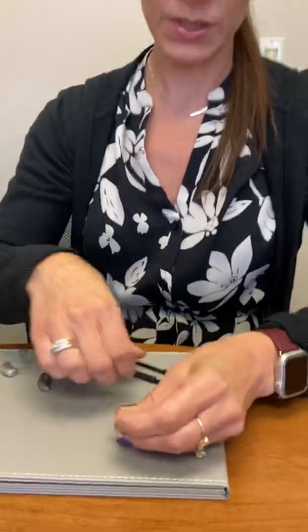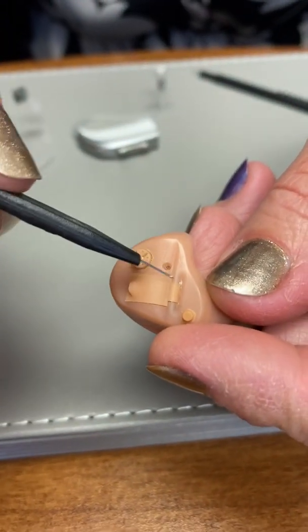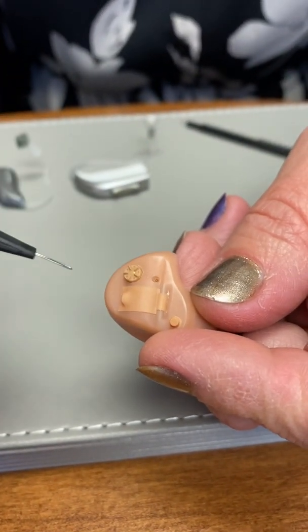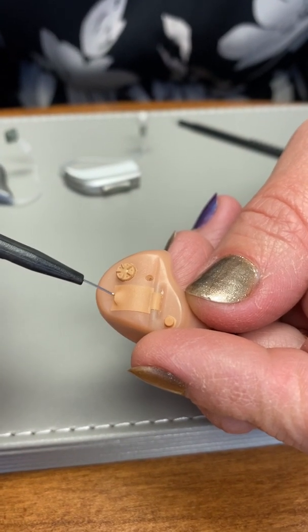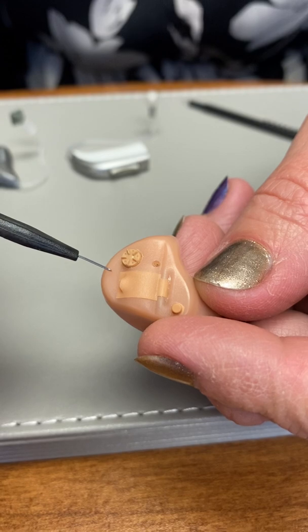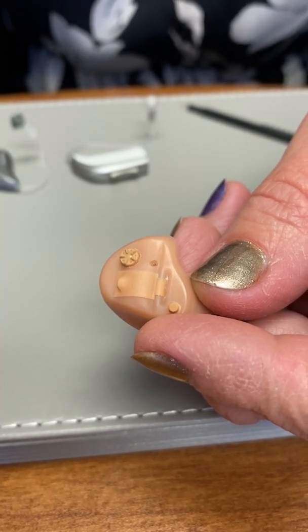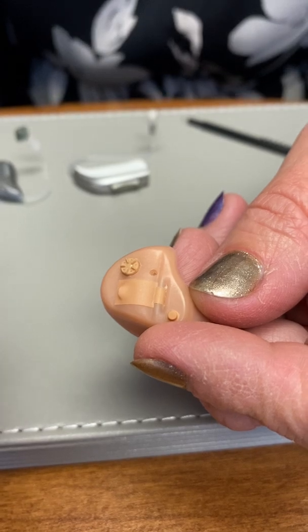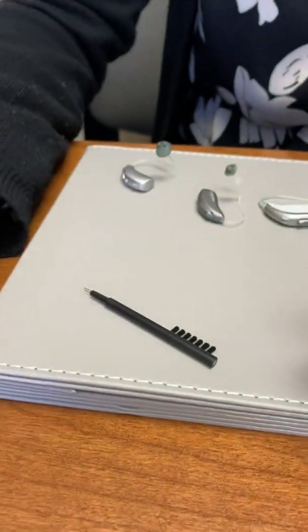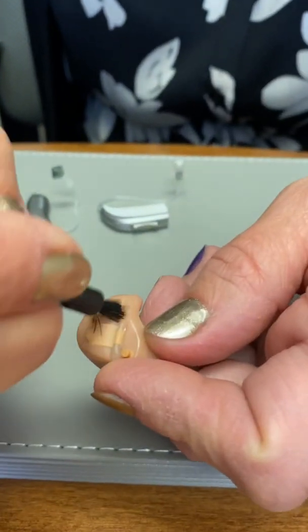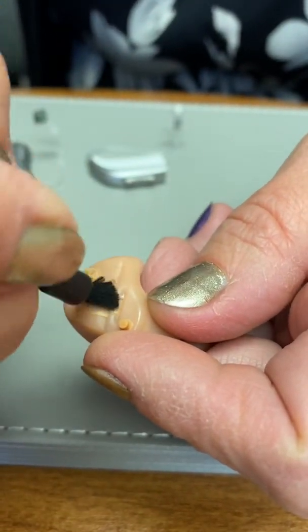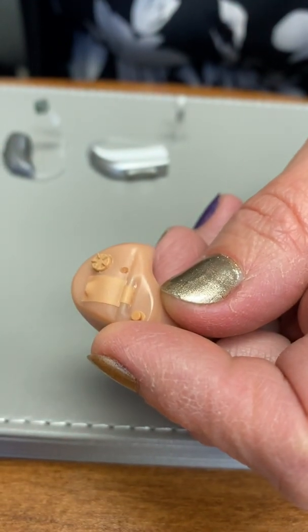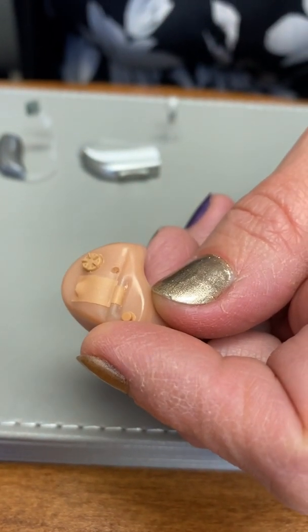So I'm going to start out with an in-the-ear hearing aid, and I'm going to go ahead and show you the ports of the microphone. On this device, there actually is only one, and it's represented by this circle right here. In most in-the-ear devices, there would be a second microphone located over here. The two will look identical. The best way to clean these is to take a brush. Either variety will work, and you just want to brush over the top of that microphone port at the end of the day to get rid of any loose dirt, dust, or debris.